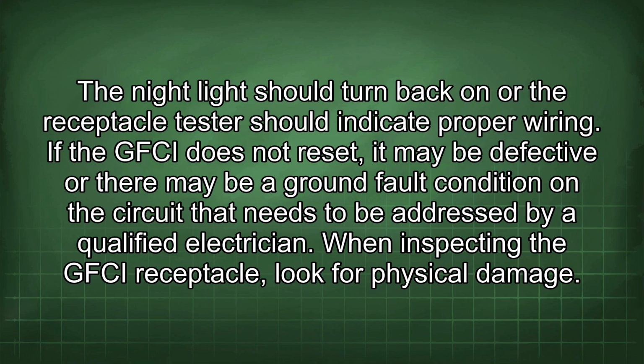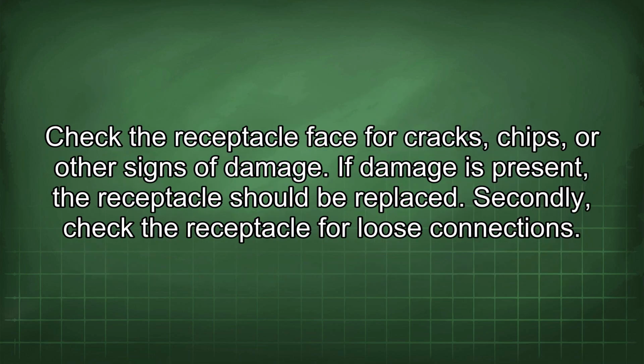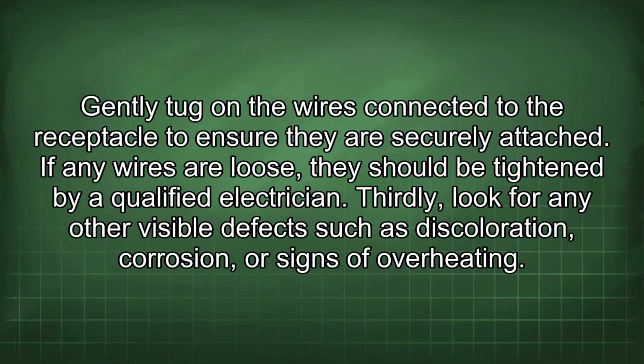When inspecting the GFCI receptacle, look for physical damage. Check the receptacle face for cracks, chips, or other signs of damage. If damage is present, the receptacle should be replaced. Secondly, check the receptacle for loose connections. Gently tug on the wires connected to the receptacle to ensure they are securely attached. If any wires are loose, they should be tightened by a qualified electrician.